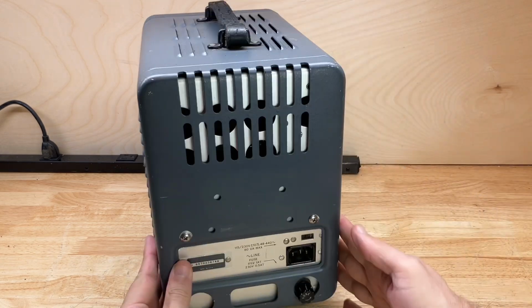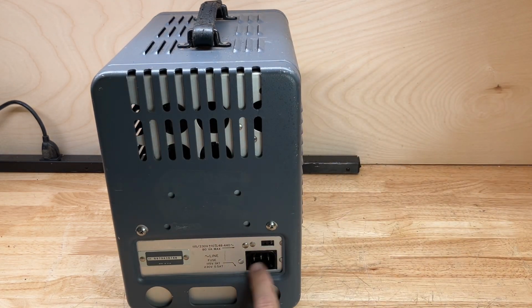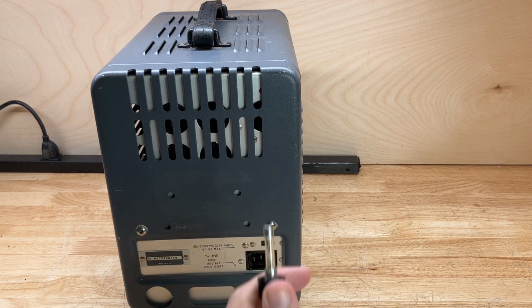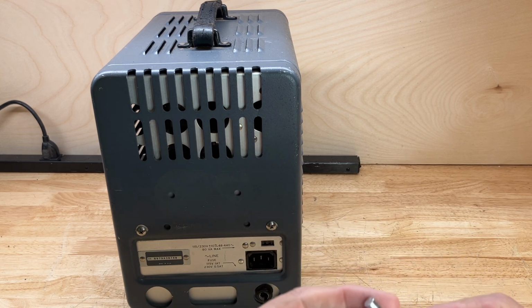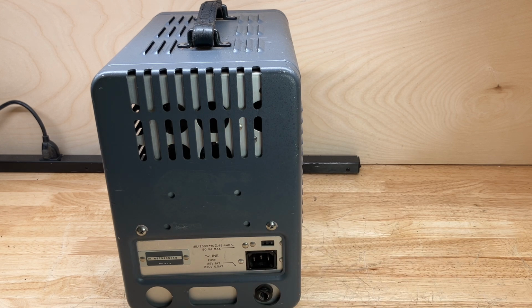What I do is check to make sure that it's set to the correct line voltage - it is set to 115 volts - and I also check to make sure the fuse is correct. Let me take a closer look. It's a slow blow, says it's a 1 amp slow blow, and according to the back here, for 115 volts it should have a 1 amp slow blow. So that is the correct fuse.